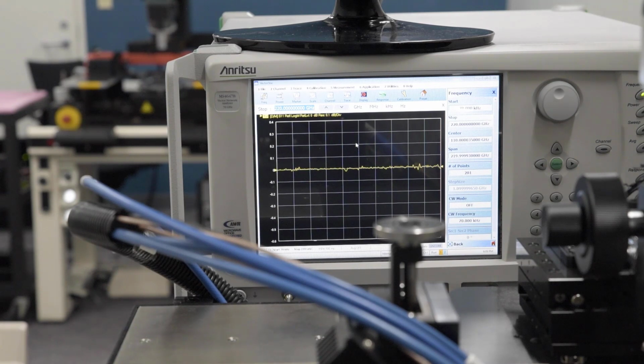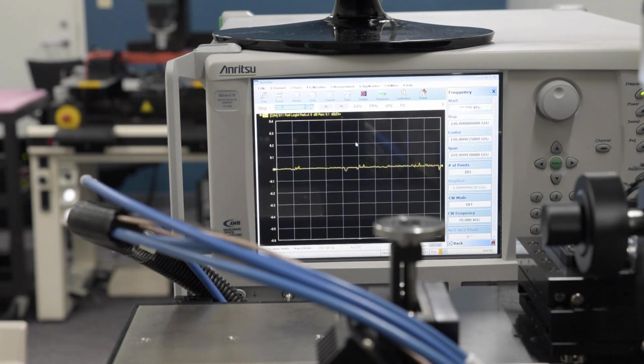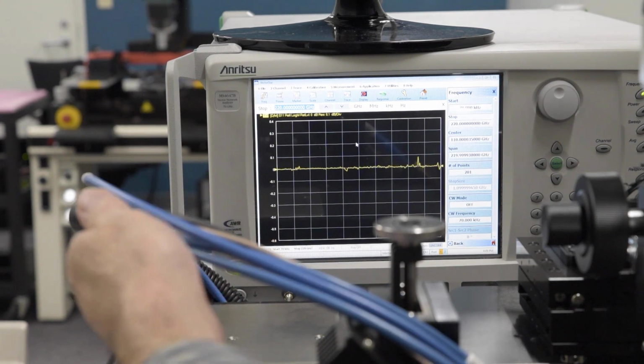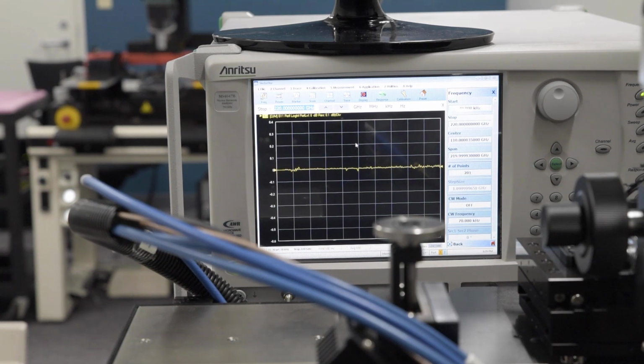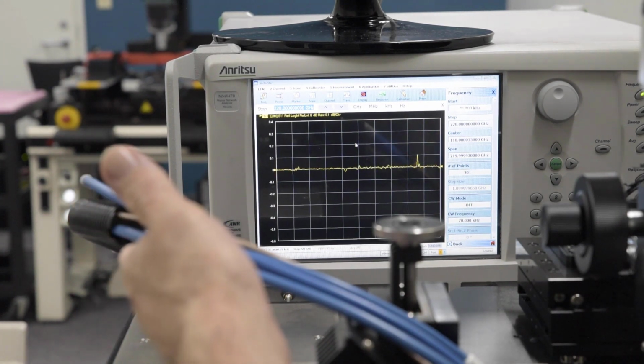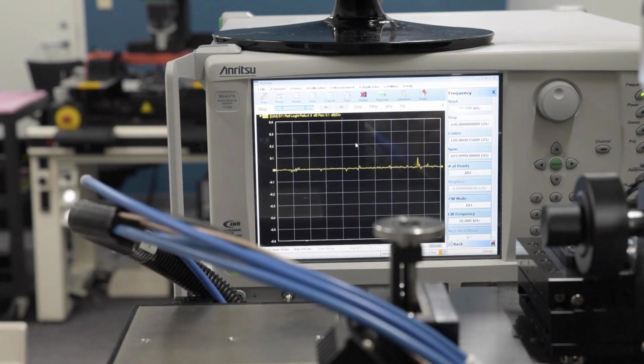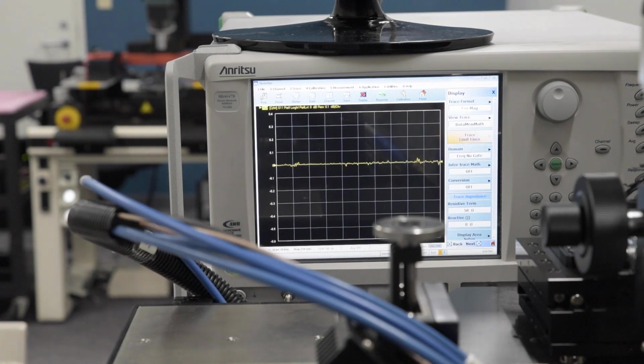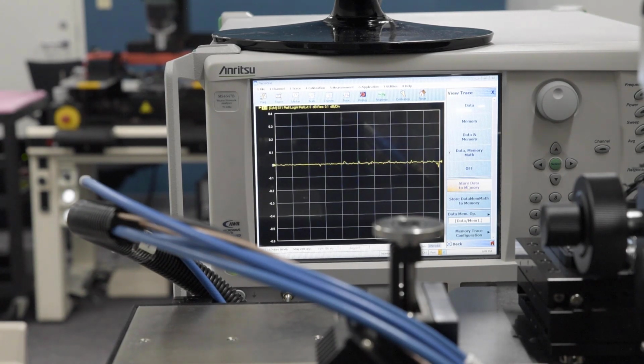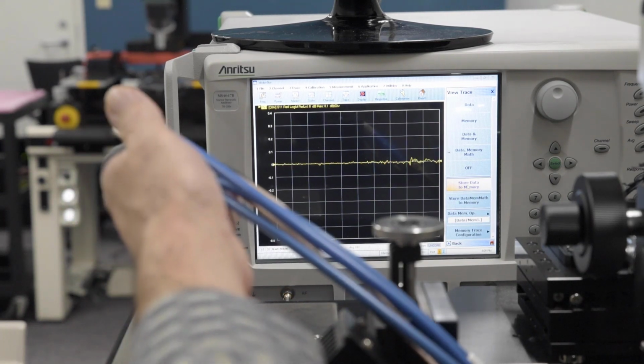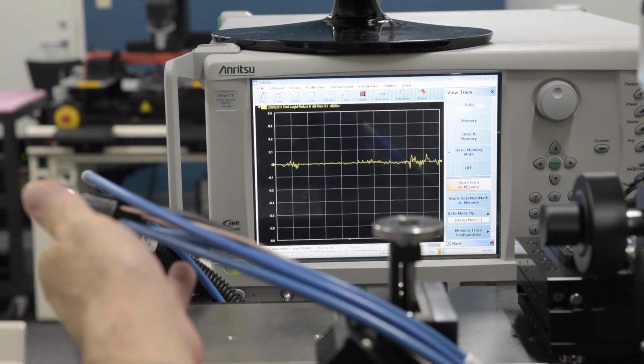If we wanted to evaluate the system sensitivity to cable flexing, we could take a look at that as well. So in this case, I've removed the cable support mechanism so that I can induce far more flex than I would normally see in my system. In order to normalize this, I'd go to my trace and store the data to memory to get a renormalization. And so now I can move my cables to evaluate.